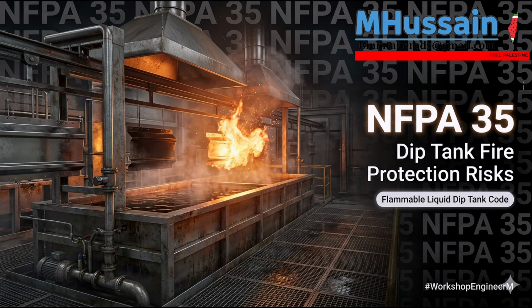So what's the rule? The standard absolutely forbids hot work unless a written permit is formally issued by a specific person in authority. But crucially, that permit is not just a piece of paper you sign in an office. It can only be issued after a rigorous physical inspection of the work area has been conducted. The area has to be sterilized of risk. Processed materials must be physically removed, equipment must be drained and purged, and the atmosphere must be scientifically tested with gas monitors to prove it is below explosive limits. Annex B of the standard actually provides a sample safety work permit and a confined space entry permit. Facility owners should absolutely adopt these exact checklists.